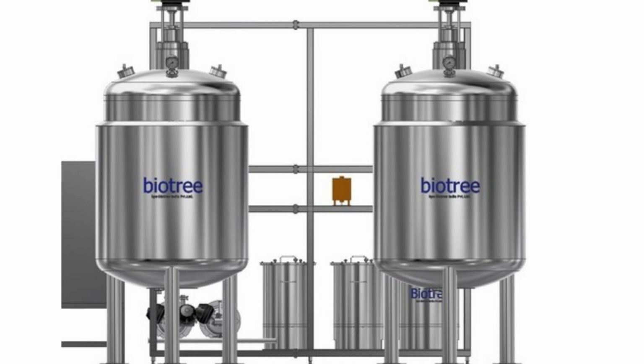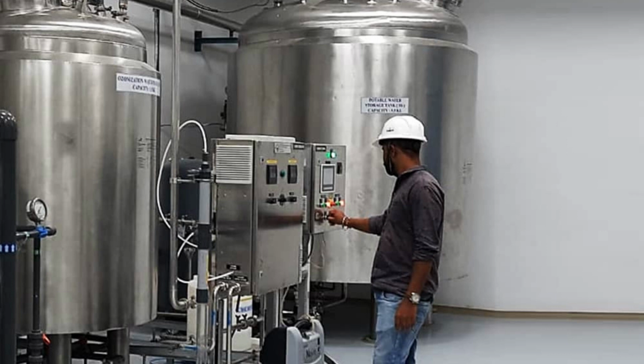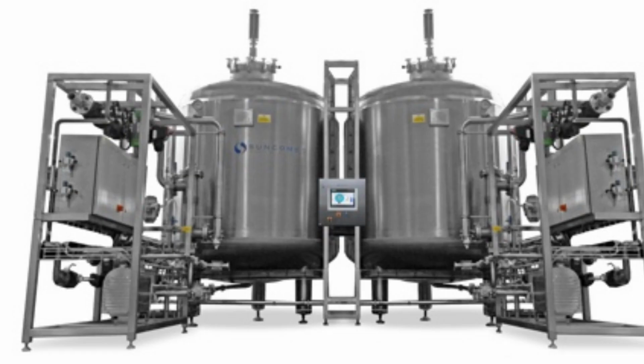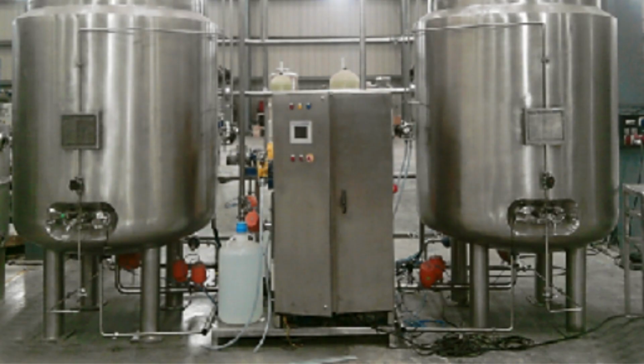Biokill systems are available in multiple sizes and configurations, which are continuous thermal bio-waste inactivation system and batch bio-waste inactivation system. Continuous thermal bio-waste inactivation system is a skid-mounted thermal biological inactivation unit that uses heat and a continuous flow, measured in gallons per minute, to elevate and hold a high temperature to destroy living microorganisms and biological wastes on a continuous basis. Cooling water and heat exchangers are used to cool the waste stream prior to discharging from the skid. Also, instrumentation installed on the discharge piping monitors and records the effluent temperature, hold time, and flow of the waste being discharged. If for any reason the wastewater does not meet dischargeable specifications, the control system automatically recirculates it back to the holding tank for retreatment.